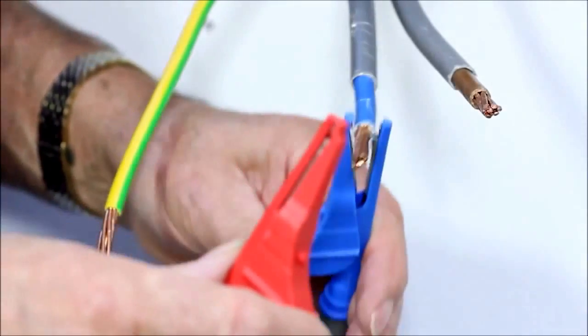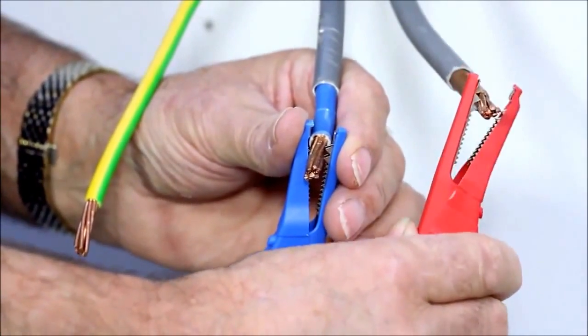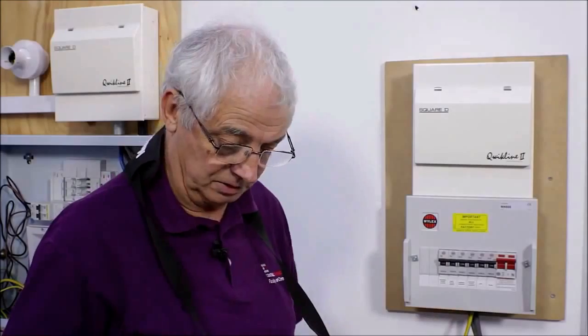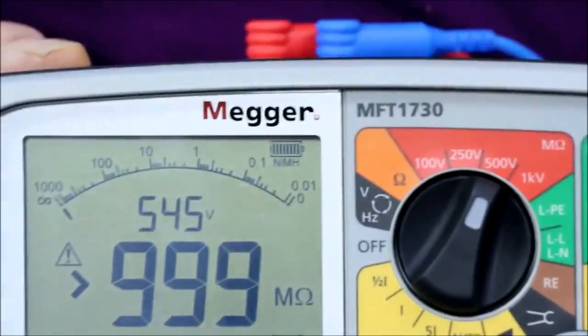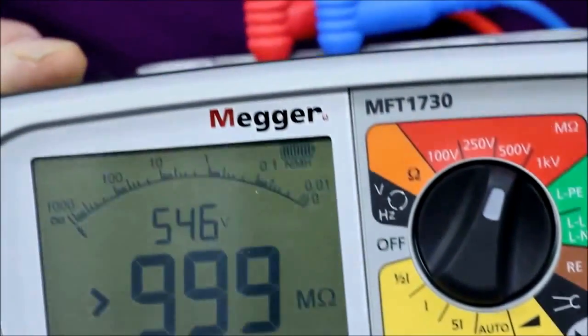First part of the test really is test between live conductors, just using crocodile clips, making sure that they're nice and tight. Push the button, and I've got a value which is 999, which is perfect. Any value over 2 megohms would be acceptable, but of course 2 megohms really seems quite low, and on a new installation we would really be looking for 999, or at least, depending on the instrument you've got, it should be over range, higher than we can measure.